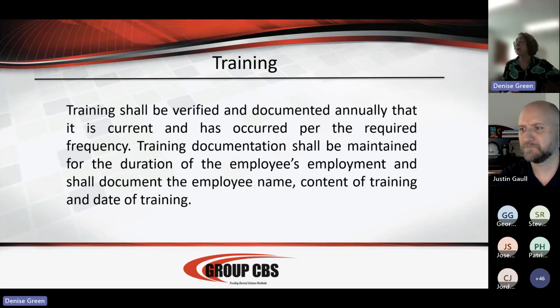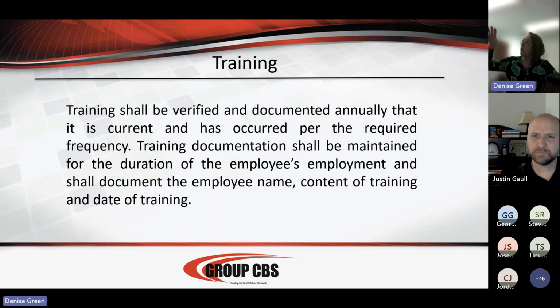Okay, so the handbook has what that is. You can look in the handbook and decide if someone in your company is qualified to provide that training. It's not anything super complex. Are we using a safety hook? What equipment are we going to have in our facility to release someone? Are we going to go through all of the ways that you can remove someone from being shocked? Make sure that there's a 2x4, that you could knock someone out of the way, use a trash can. They don't have anything specifically spelled out on that. So I advise you to look at the handbook, see what the handbook specifies, and that's usually something you can handle in-house. That's going to go hand in hand with your electrical safety program.